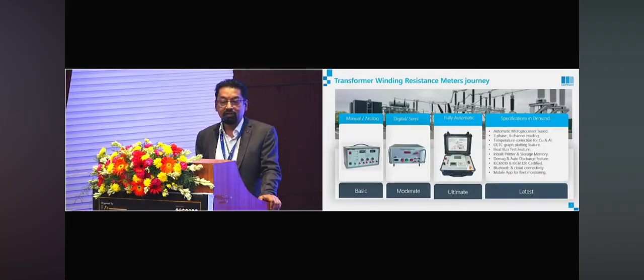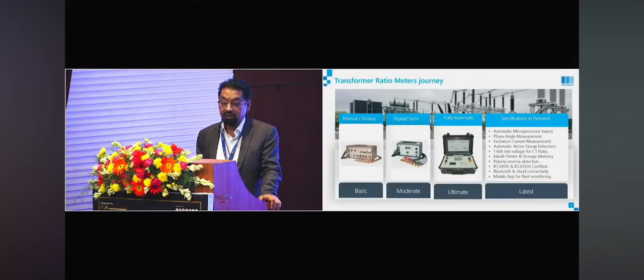So people are expecting more from the existing equipment. The same thing is happening with the ratiometer. Manual balancing became semi-automatic and now fully automatic. Here people are demanding automatic vector group detection, not only vector group comparison. They want automatic detection, because for old transformers where there are no nameplates, the equipment should detect the vector group automatically. Vector group verification is one thing, where you have to enter and check whether the same vector group is there. But automatic detection of the vector group is becoming more and more popular.